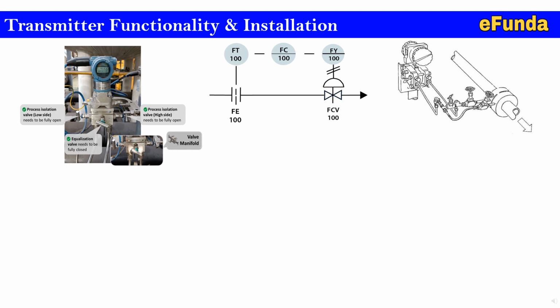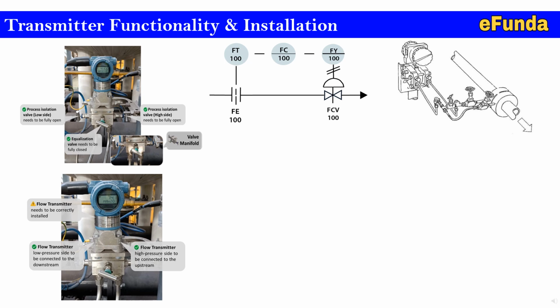One can refer to the picture from the Emerson transmitter where the process isolation valve, that is the low side valve, needs to be fully open. The process isolation high side valve needs to be fully open. In the center one can see the equalization valve needs to be fully closed. Valve manifold, one can see in the small picture. Simultaneously, in another picture one can see the electronic transmitter body, that is a flow transmitter, which needs to be correctly installed. Then below the flow transmitter, the low pressure side is to be connected to the downstream of the line, as well as the flow transmitter high, that is the HP side, is to be connected to the upstream. This is how the installation of a flow transmitter is done in the field.